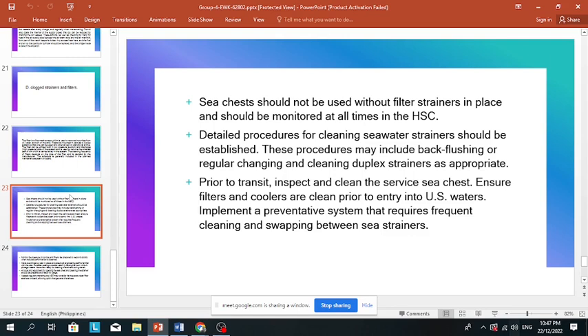Sea chest. The sea chest should not be used without filter strainers in place and should be monitored at all times in the HSC. Second, detailed procedures for cleaning seawater strainers should be established. These procedures may include back flushing or regular changing and cleaning of duplex strainers as appropriate. Third, prior to transit, inspect and clean the service sea chest. Ensure filters and coolers are clean prior to entry into US waters. Implement a preventative system that requires frequent cleaning and swapping between sea strainers.